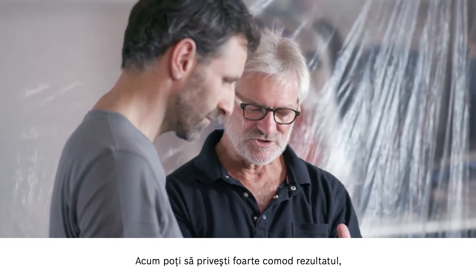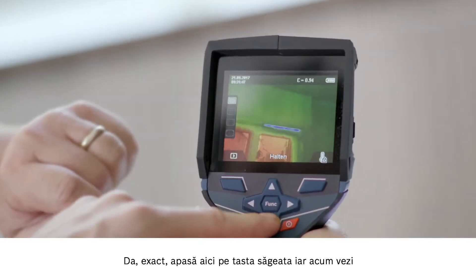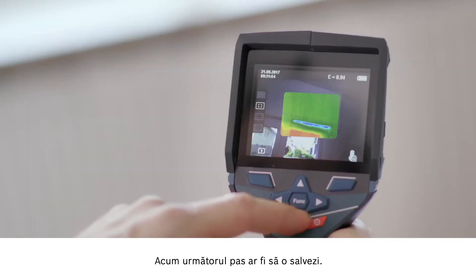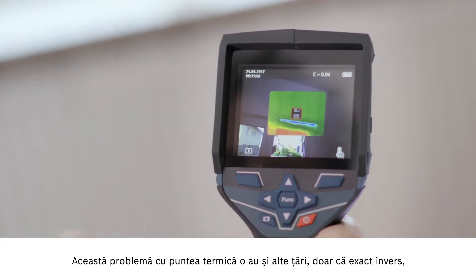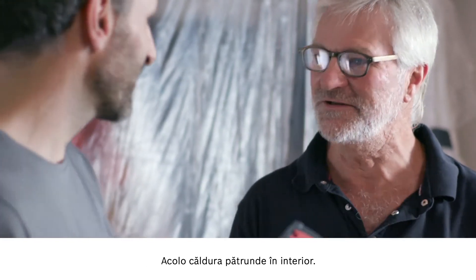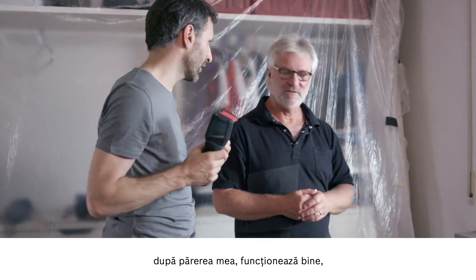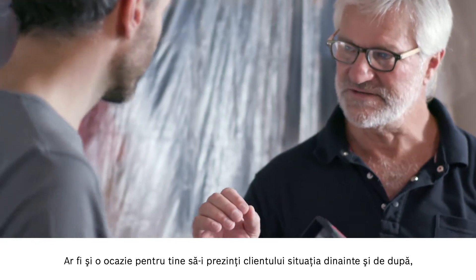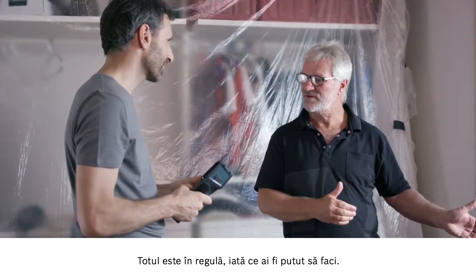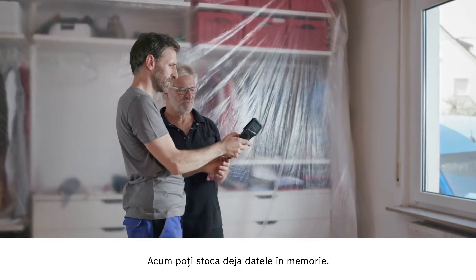Now it's really easy to view the results, and you can even zoom in on a real image by pressing this button here. Press the arrow button and you'll see the real image — that way it'll be easier for you to show your customer where exactly you measured. The next step is to save what we've done. In other countries they have the exact opposite of this thermal bridge issue with air conditioning systems — in practical terms it's the same problem, the heat is getting in. One more thing with the heating: I bled it earlier and believed that it's all working properly, but we can check that now too. Just press the button, start scanning like before, and then save. You can look at what you've saved to the memory right away.